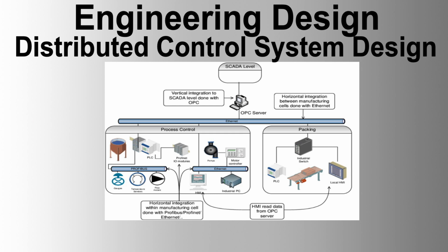The DCS vendor must provide detailed grounding requirements and installation details, ensuring separation of the system ground from other grounds. Detailed specifications for communication bus error detection and correction, transmission speed, and communication methods must be provided. Communication buses must be supplied by the vendor, and each system cable must be permanently identified and approved by the purchaser.